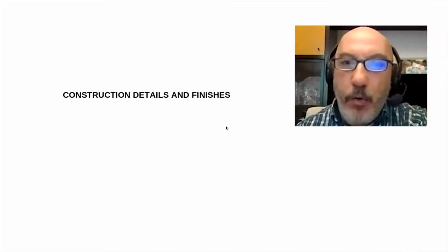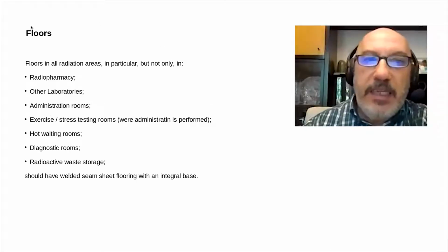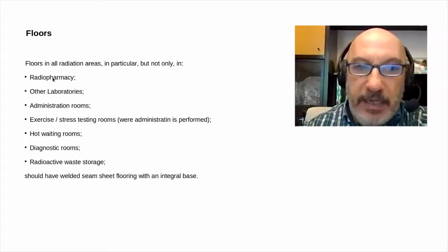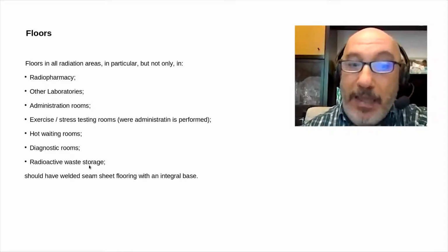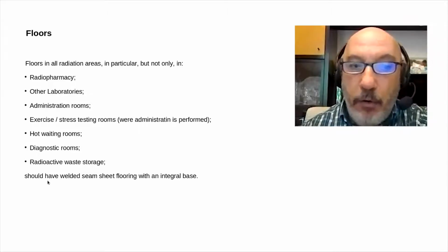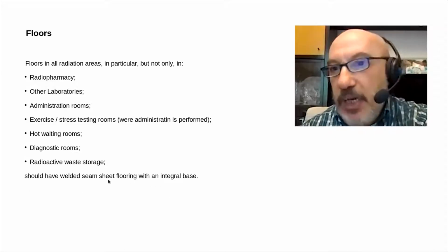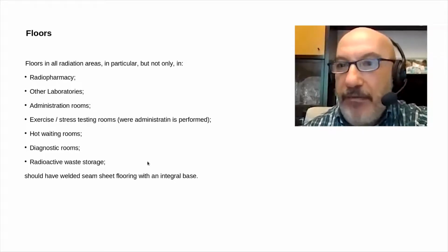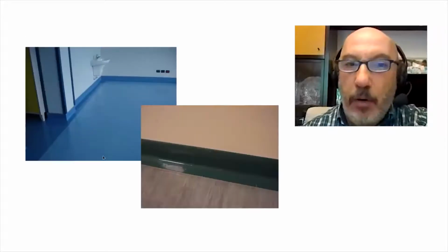Let's now give a look at some specific details and finishes in the construction. Let us speak about floors. In all the radiation areas, but particularly in radiopharmacies, in administration rooms, in stress testing rooms, in hot waiting areas, in diagnostic rooms, and in waste storage, floors should be decontaminable. So they should possibly be realized in sheets of plastic material welded to each other in order to be continuous and not have any discontinuity that may allow for the formation of deposits of any residual contamination.